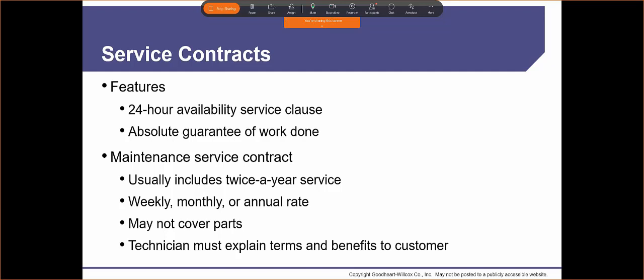When we talk about a maintenance contract, there's usually twice a year service. We're going to do the AC system, and then we're going to do the furnace when it's time. Here, we usually don't start doing air conditioning service until we're above 60, 65 degrees, just because of how the refrigerant is. And so that means we're not really going to be doing service on air conditioning systems until end of April, early May. The last couple of years, we went from 50 degrees, all of a sudden we jumped up to 80 in no time. Well, there we go. We didn't really have too much time to do too many service calls or PMs, and we started hot right out of the gate.